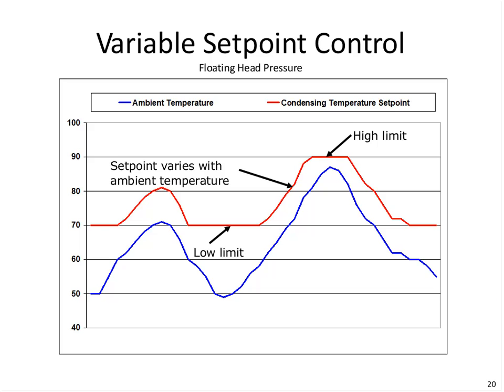So here, let's see. If the ambient temperature is up here at around, let's say, 85, 86 degrees, and all fans are going full speed, everyone grab your arrow and point it somewhere on this chart where the likely condensing temperature would be at the peak of the second day here. It says high limit, but that's not necessarily the temperature we'd be condensing at. The condensing temperature is going to be ambient plus whatever the condenser can do.